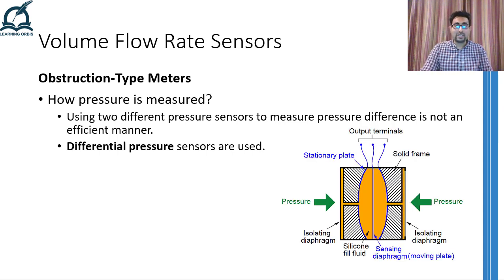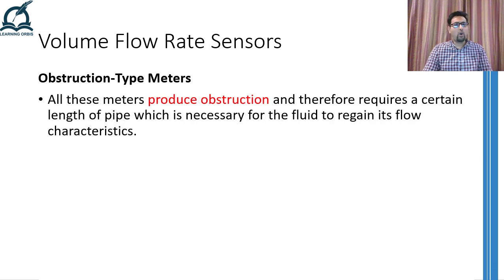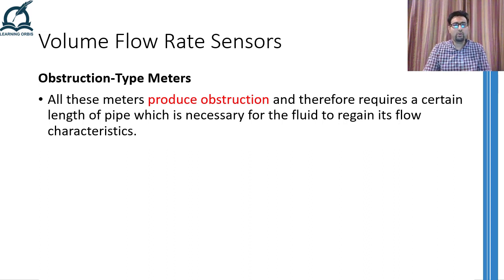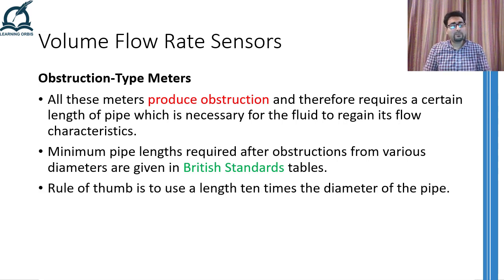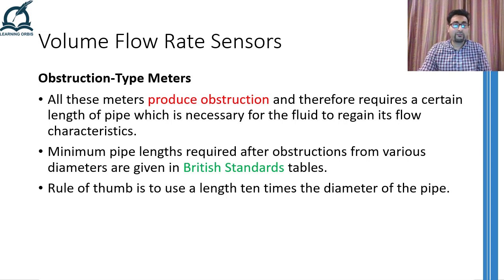Mostly diaphragm type pressure sensors are used in such situations. As all obstruction type meters produce a permanent pressure drop and disturb the flow characteristics, a certain length of pipe is required after the obstruction for the fluid to regain its flow characteristics. How much length of straight pipe is required can be found using British standard tables. However, especially in process industry, a rule of thumb is to use at least a length equal to 10 pipe diameters after the obstruction.